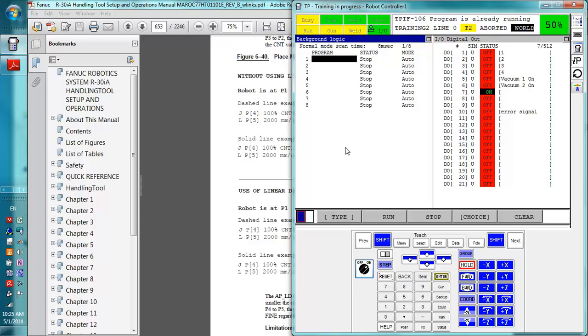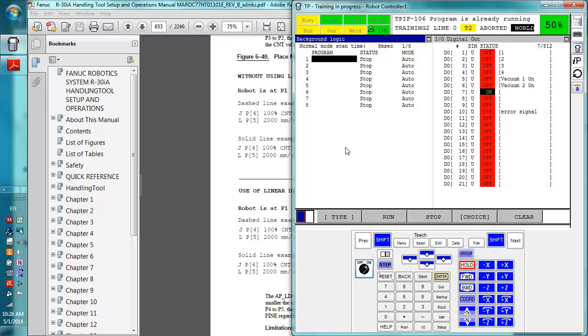It was constantly running as fast as it could so as to update the PLC as much as possible. This can be slightly faster than a parallel program because it's not restrained as much. The way parallel programs work in FANUC is it'll actually run a section of code in one of the programs, then switch over and run a section of code in the other program, switch back over, run a section of code in the first program, then switch to the second one, run a section of code.